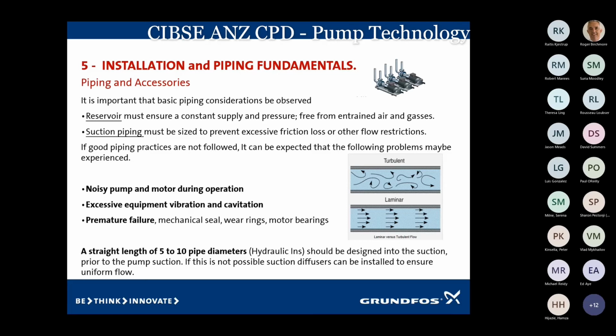We like to have a laminar flow entering into the pump where you can see the water's nice and smooth and it's entering in, because it's got to get into the impeller of the pump and then it's got to get itself out of there again. If the water coming into the pump is turbulent, it's going to hit that impeller, it's going to be noisy, it's going to transfer that vibration down the shaft into the motor bearings and into the mechanical seals. And over a period of time, we're going to have to get in there and service it.